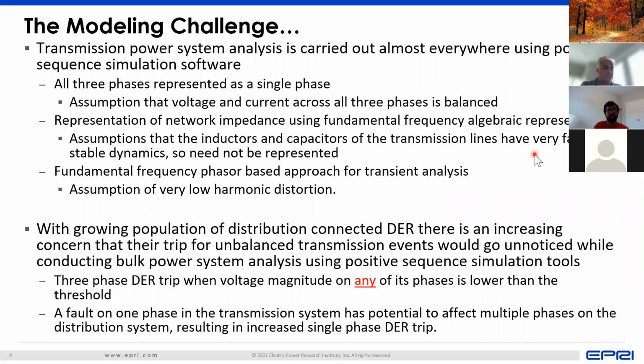The main thing to consider is that transmission system analysis is usually carried out in something called positive sequence simulation software. What positive sequence software means is that even though the power network has three phases, your A, B, and C, or your red, blue, and yellow, however you denote them, we assume at the transmission level that everything is balanced, that the voltage and current across all three phases are balanced, which means that all three phases in a way behave as a single phase. Because what happens on one phase, we can easily translate into the other two phases. So we represent the entire transmission network as a single phase, even though there are actually three phases.